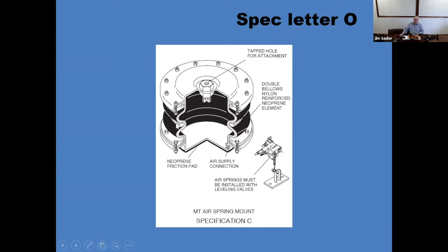With an air spring, we have a rubber bladder that's capped on the top and bottom, and there's pressurized air inside that supports the equipment. And the advantage is it has a low natural frequency, but the other advantage is that high frequency noise cannot get through this rubber bladder. There's too much impedance.